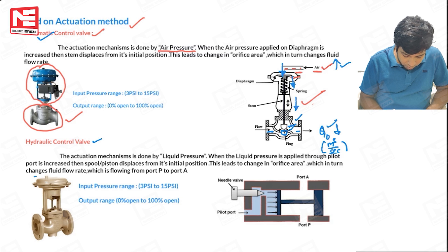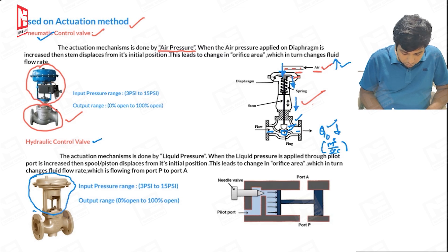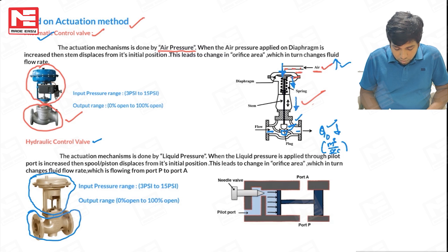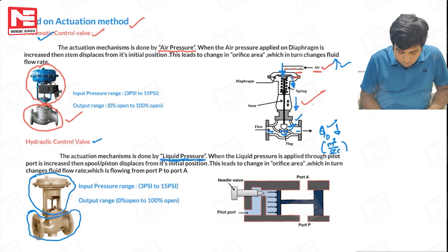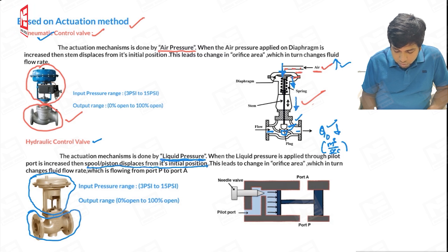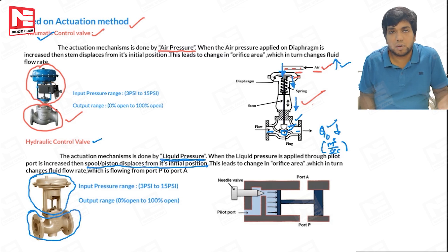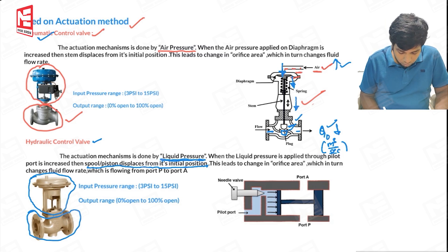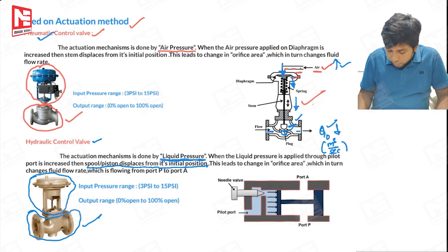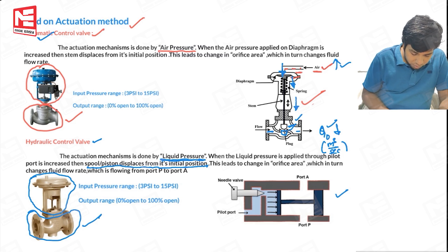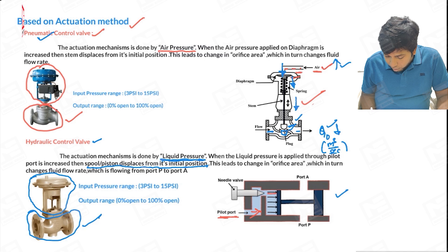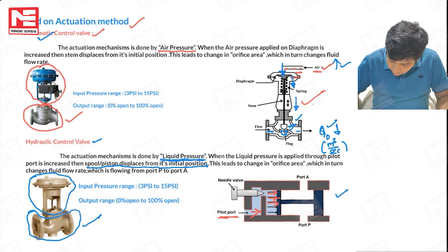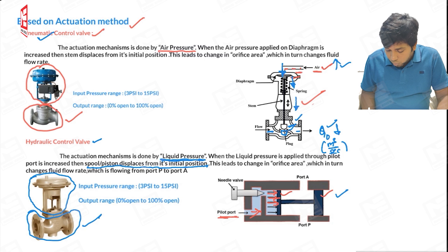The second type is the hydraulic control valve. Again, the upper part is called the actuating body and the lower part is the control valve body. In this case, the actuation mechanism is done by liquid pressure. When liquid pressure is applied through the pilot port and increased, the spool or piston displaces from its initial position, leading to a change in orifice area and naturally a change in flow rate.